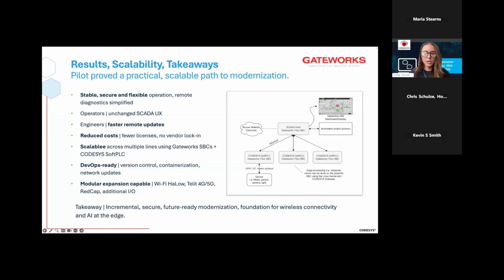The real business value for them was that when updating old PLCs, they used to need a licensed Windows machine, special cables, and vendor software. Now with a CODESYS soft PLC, updates could be pushed directly through the network or via remote secure access. And because it's Linux-based, engineers could use standard DevOps practices, version control, remote monitoring, and containerization, something simply not possible on closed PLC hardware.